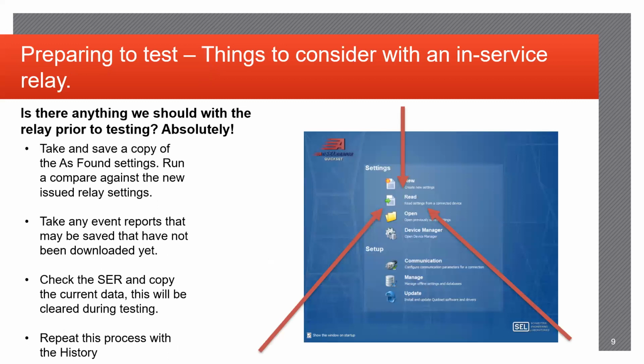So preparing to test, things to consider, especially with an in-service relay. So say we start with an in-service relay, we've correctly isolated it, are 100% sure that the relay will not misoperate when testing, nothing's connected to it. It's literally just the relay and its DC source for power. So if it is a previously in-service relay, the first thing you always want to do when you hook up to the relay is read the as found settings. This is extremely, extremely important, not only to you, but to the client, to correctly identify that you have a record of the previously in-service settings.